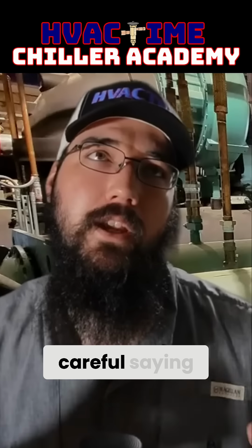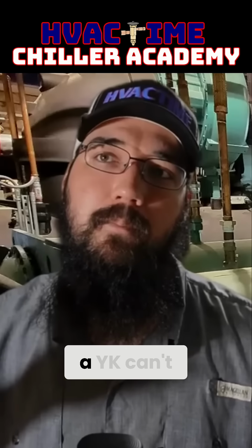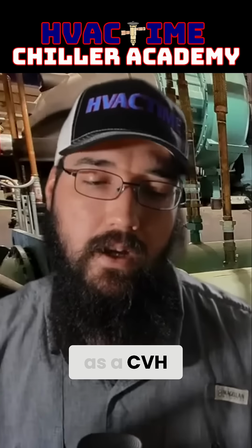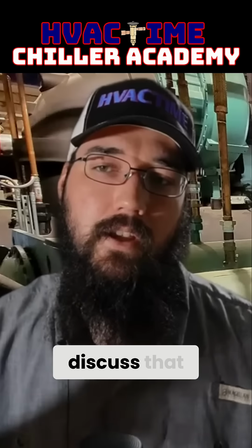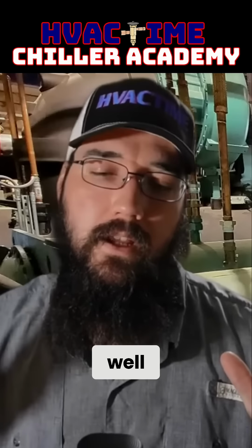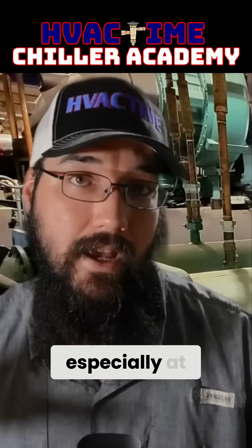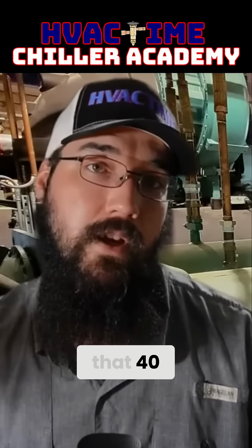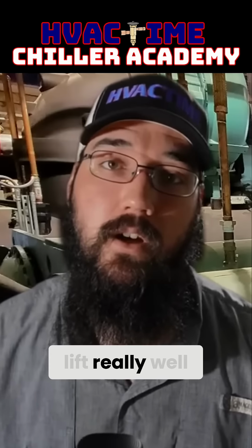I want to be careful saying it that way, but a YK can't handle high lift as well as a CVH, but we can discuss that they run really well in say a 25 to 45 degrees of saturated lift, especially at load. So at load, they can both push that 45 degrees of saturated lift really well.